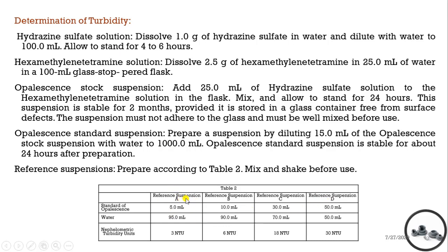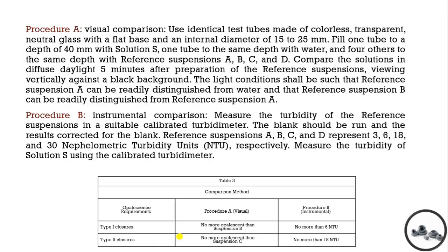For example, for reference suspension A, we take 5 ml of the opalescence standard and dilute it with 95 ml of water. We measure its turbidity in a nephelometer and it should be 3 Nephelometric Turbidity Units (NTU).